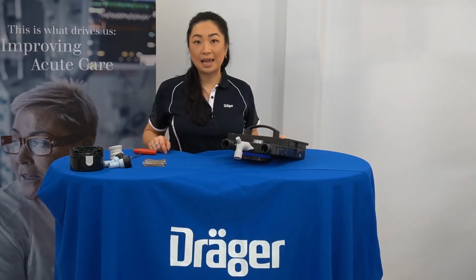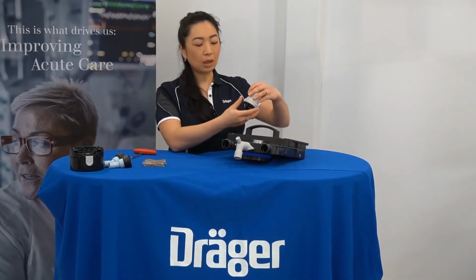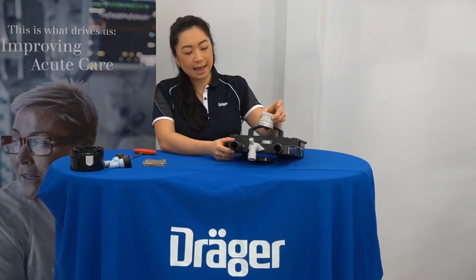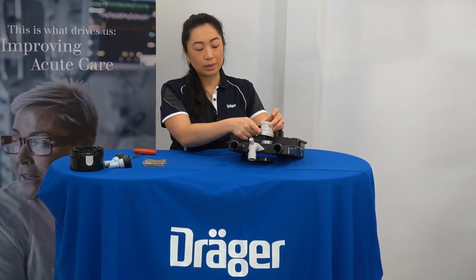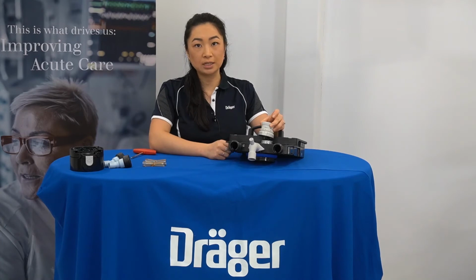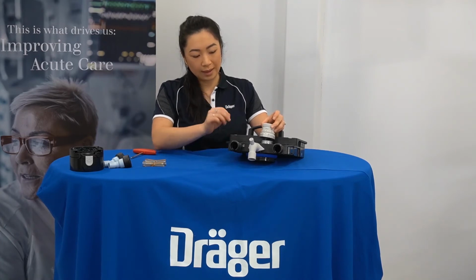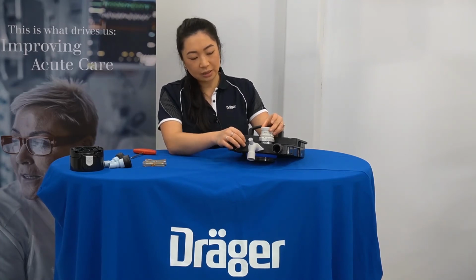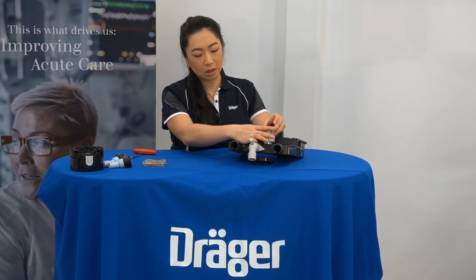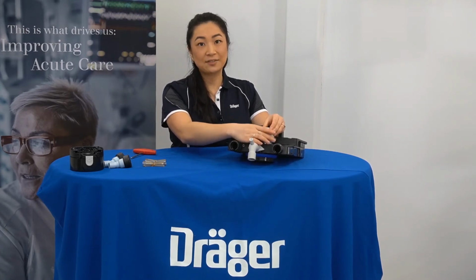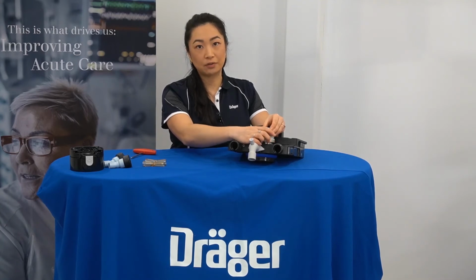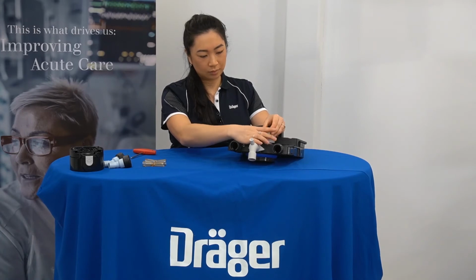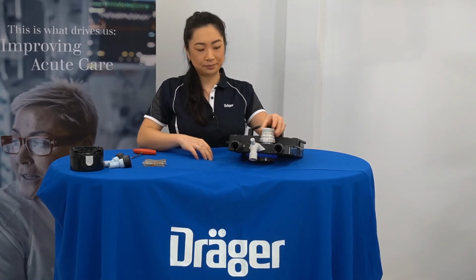To return the APL valve, with one hand, steady the APL valve in position with the dot lining up to the front of the breathing system. With the other hand, position the valve and properly thread the lower component on. If resistance is felt, readjust the APL valve. And just ensure to tighten it so that it is finger tight.